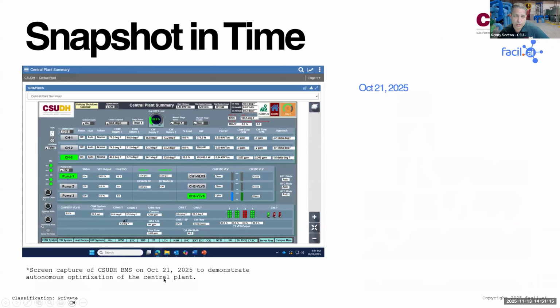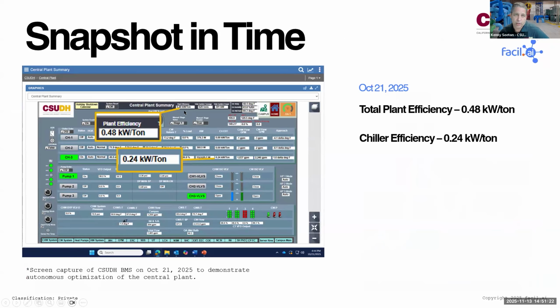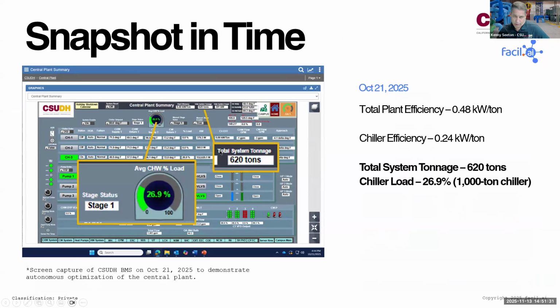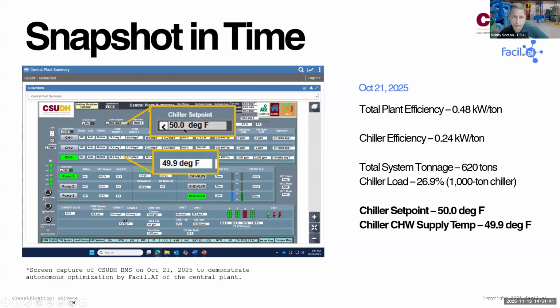So here was a snapshot we did October 21st, 2025. This is a central plant summary page. At this time, the total plant was running at 0.48 kW per ton, and the chiller was actually running at 0.24. We were doing 620 tons with a 1,000-ton chiller, and our load was only 27%. We were doing 50 degrees. There are a lot of things that come into play here, right? What's the temperature that you're running? What's the outside air? What's the wet bulb? All those things we're inputting into the AI, and it's changing the condensing water temperature set point.